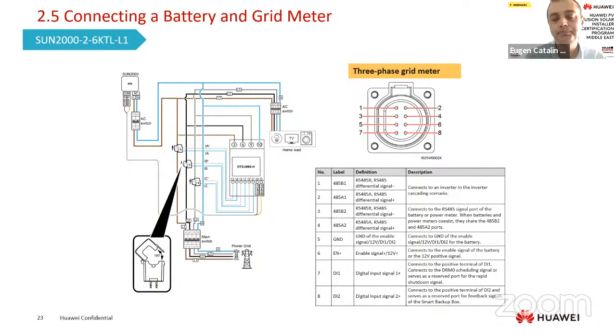If one of the phase powers, for example phase B, is in minus, it means that the current transformer is installed in reverse. So you need to change the connection here. Maybe you installed the current transformer as blue, white instead of white, blue, and this means you reversed the sense of the current transformer. So you will check the cable, or you will check the arrow of the CT. This is very important for the meter to work correctly, because the meter will send the information to the inverter, and the inverter will act.